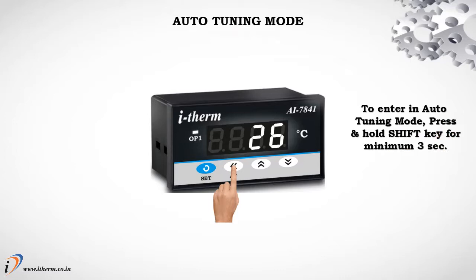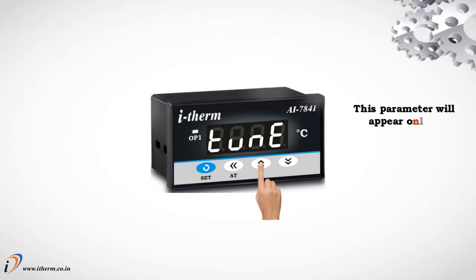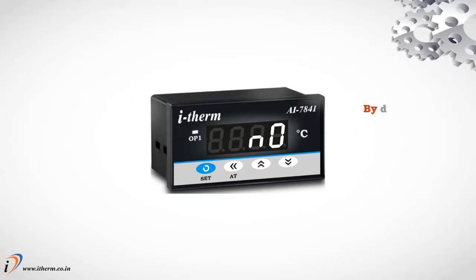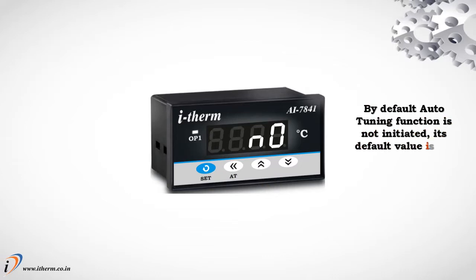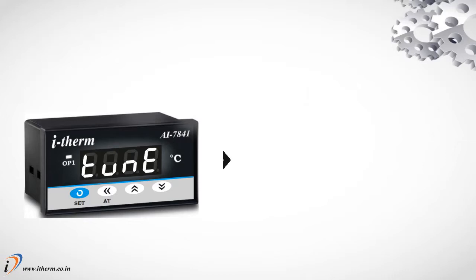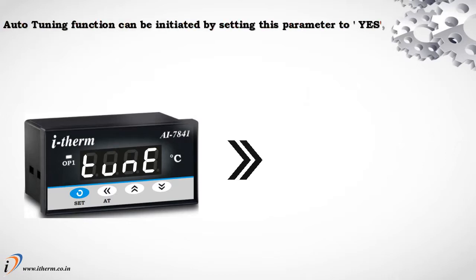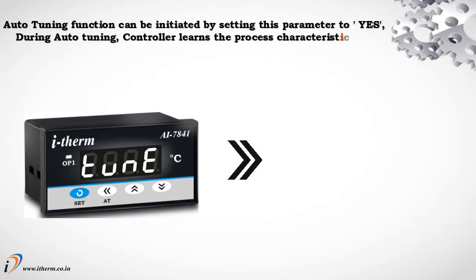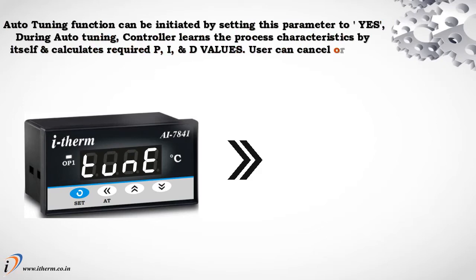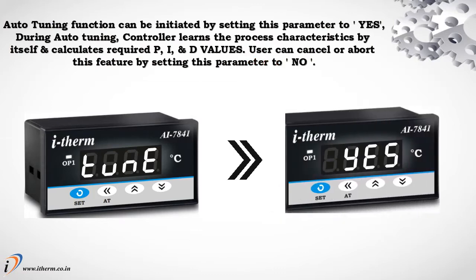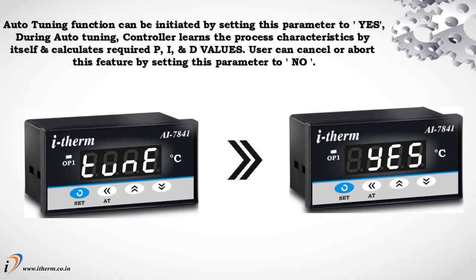Press and hold Shift key for minimum 3 seconds. Parameter 1, auto-tune. This parameter will appear only if auto-tuning function is not initiated. Its default value is no. Auto-tuning function can be initiated by setting this parameter to yes. During auto-tuning, controller learns the process characteristics by itself and calculates required P, I, and D values. User can cancel or abort this feature by setting this parameter to no.